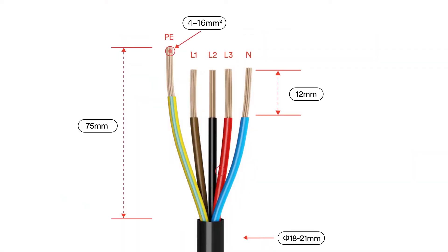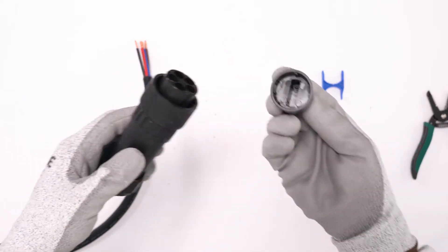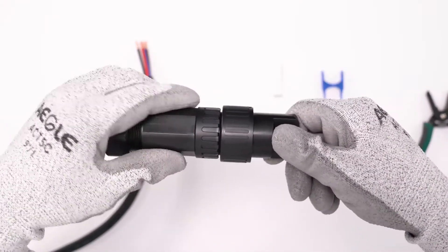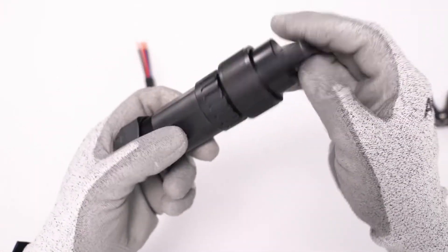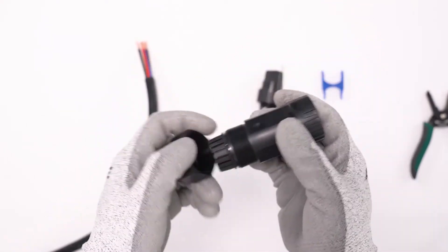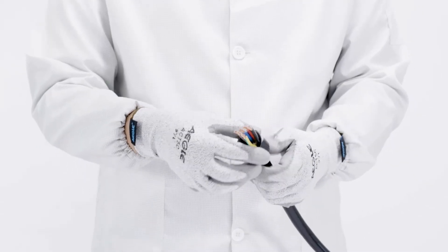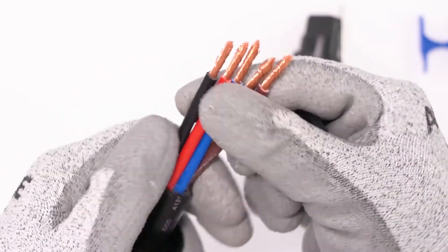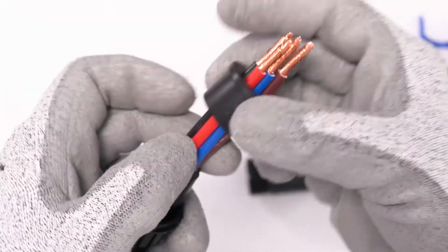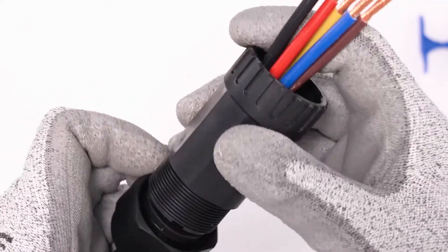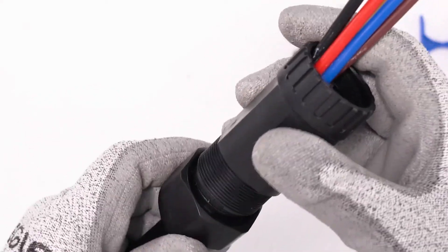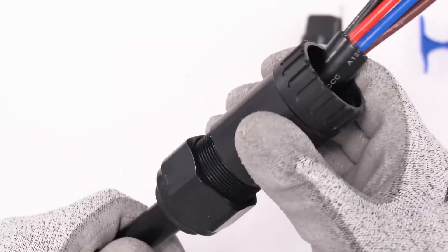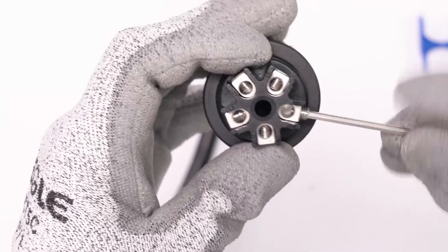The AC cable requirements are as follows. Loosen the swivel nut of AC connector. Insert the crimped conductors into corresponding terminals and tighten screws with the accompanied Allen key. Insert the adapter to the socket element. Stuff the seal ring into the adapter and tighten the swivel nut.